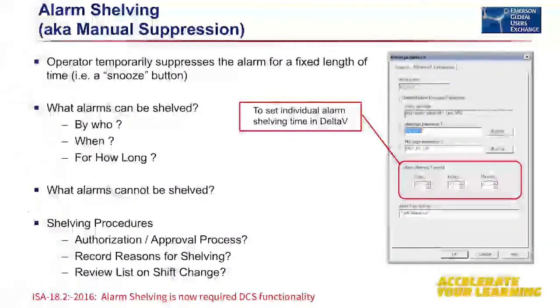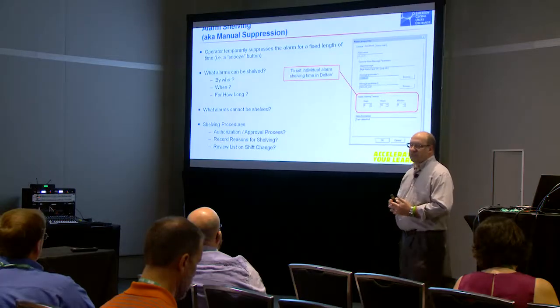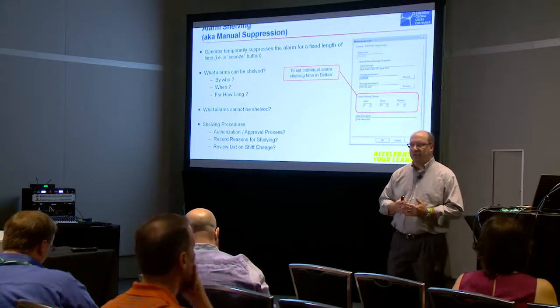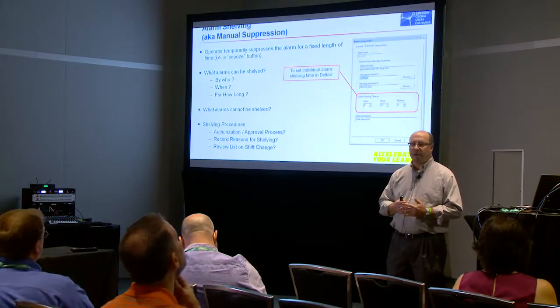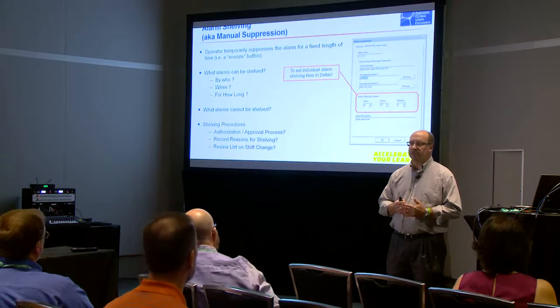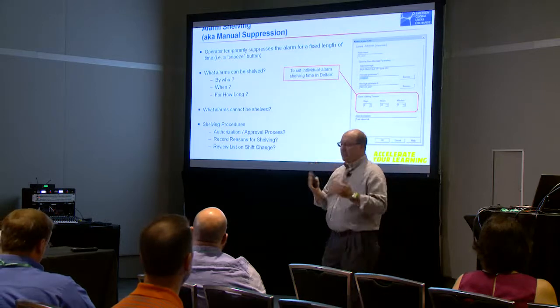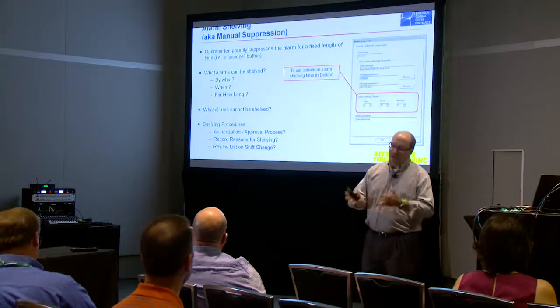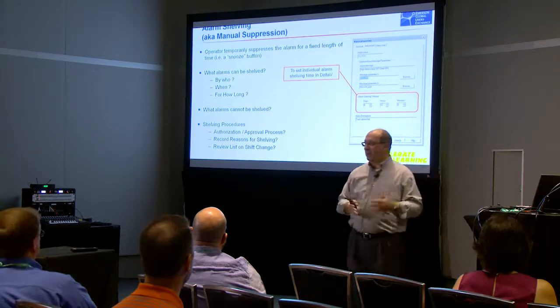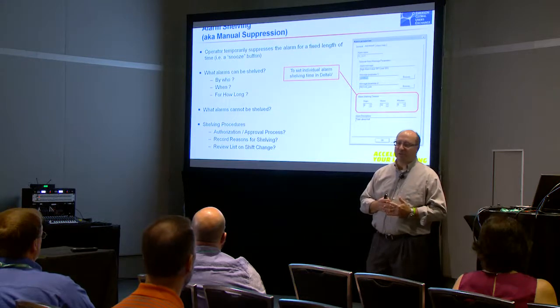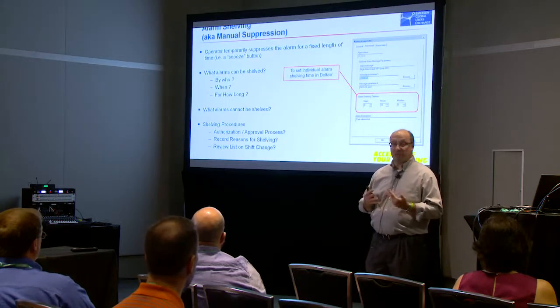So let's talk a little bit about how you would decide how to take advantage of them. The first one is shelving. This is the temporary suppression of an alarm by the operator. I've talked to a lot of end users that are concerned about allowing their operators to shelve alarms, to suppress alarms. Some people don't think that's a good idea. Well, if you feel that way, go sit in the control room when you have a chattering alarm going off every 5 minutes and see how easy it is for the operator to do their job. Hopefully you'll realize that there is a time and a place for allowing operators to do this shelving.